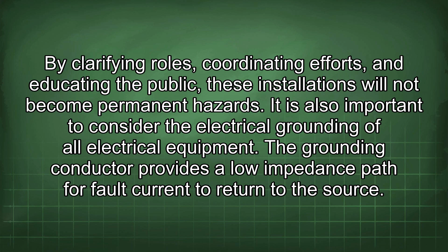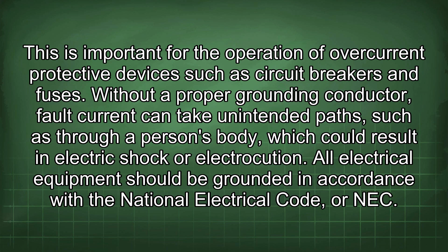It is also important to consider the electrical grounding of all electrical equipment. The grounding conductor provides a low impedance path for fault current to return to the source. This is important for the operation of overcurrent protective devices such as circuit breakers and fuses. Without a proper grounding conductor, fault current can take unintended paths, such as through a person's body, which could result in electric shock or electrocution. All electrical equipment should be grounded in accordance with the National Electrical Code, or NEC. The NEC provides detailed requirements for grounding electrical systems and equipment. These requirements are designed to ensure the safety of people and property.